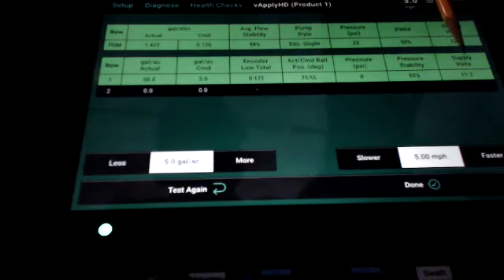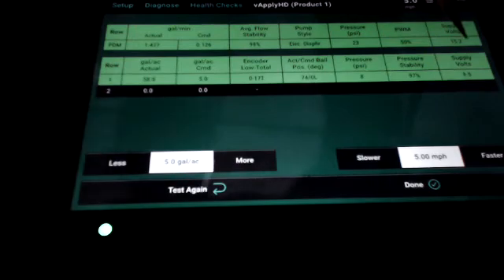And look at our supply volts, jumping around, which would also be indicative of potentially a bad circuit board within the HD itself. So we would have to try a few different components on this HD to actually figure out which one it was, but I just wanted to show you this is basically running wide open. Our pressure is way down there because we're probably maxing the pump out on this little test stand, but we're way over applying on our rate.